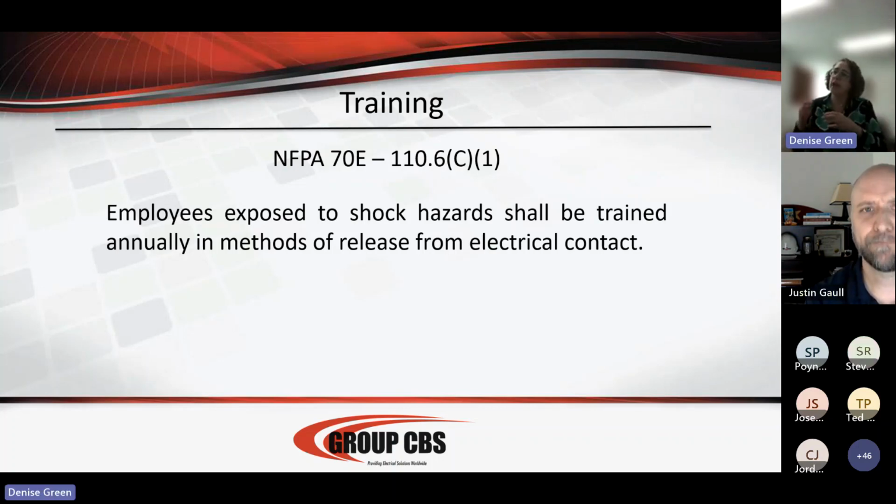Yes and no. It partially covers it, but you're only doing the avoidance of arc flash, and there's not that component of shock hazard and what exactly is your shock hazard associated with the arc flash. It is definitely a hand-in-hand training that goes with it, and that does count for some of it. But that's going to be a plant by plant, staff by staff decision. If you did 16 hours of arc flash and shock hazard training, then the next cycle, remote racking, on how to use equipment to stay out of the arc flash hazard, the customer would have to decide if that's adequate or if they combine that with additional refreshers.